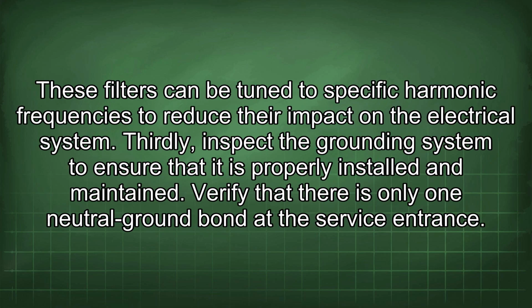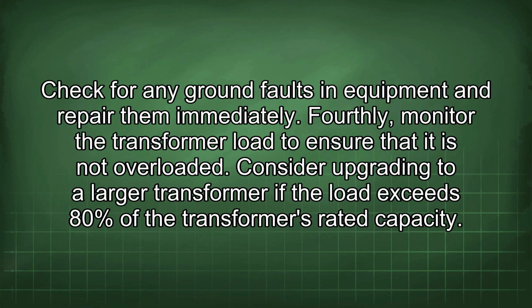These filters can be tuned to specific harmonic frequencies to reduce their impact on the electrical system. Thirdly, inspect the grounding system to ensure that it is properly installed and maintained. Verify that there is only one neutral ground bond at the service entrance. Check for any ground faults in equipment and repair them immediately.